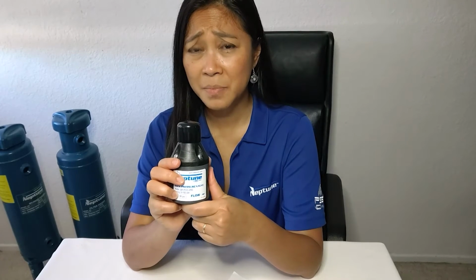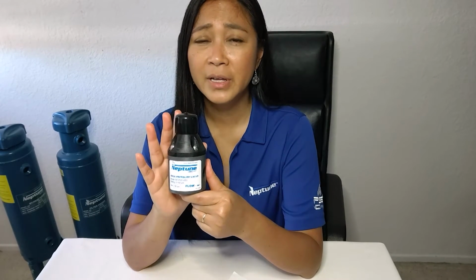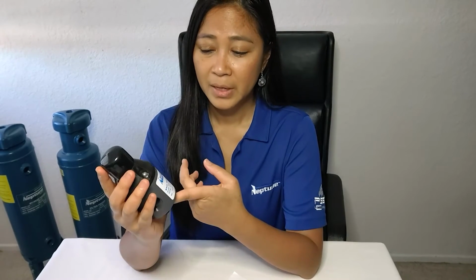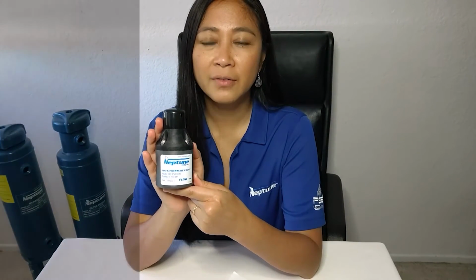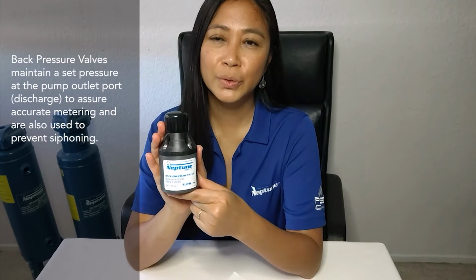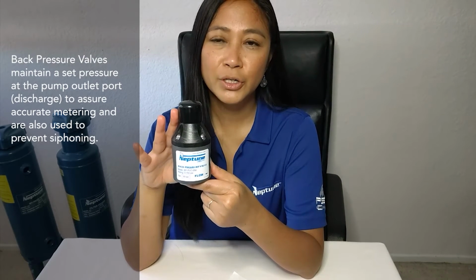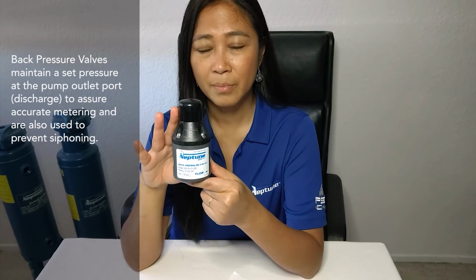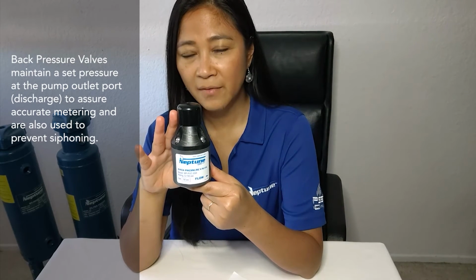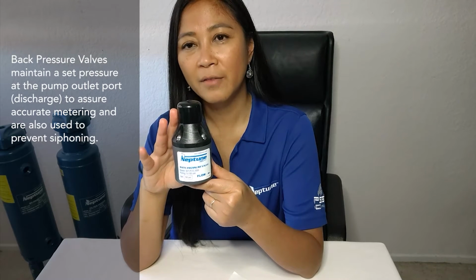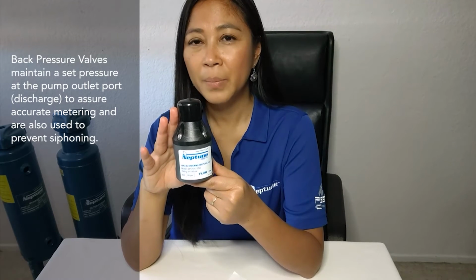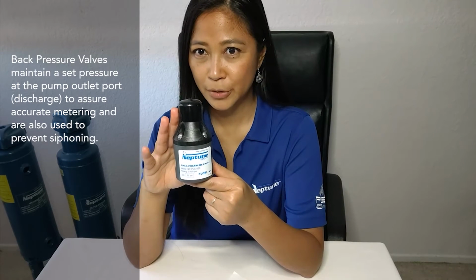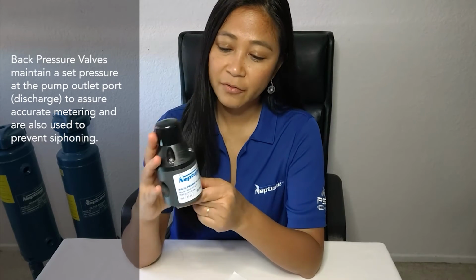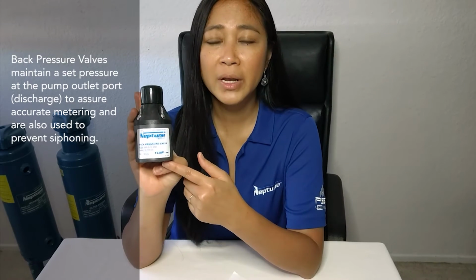Another product and accessory that I like to share its technical aspect is the back pressure valve. The back pressure valve is a device that restricts the flow coming through by putting the pressure back against the pump. In other words, it prevents siphoning. A back pressure valve is used when pumping into low pressure situations. The specification for our back pressure valve is that the pressure is rated up to 150 psi.